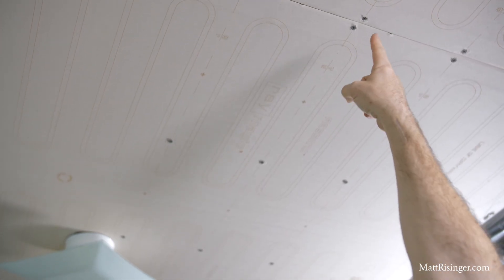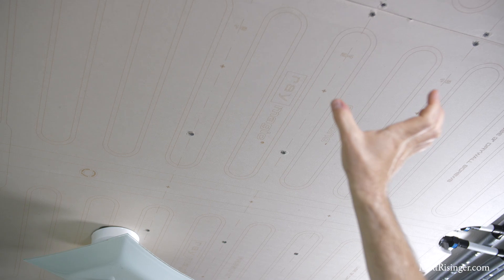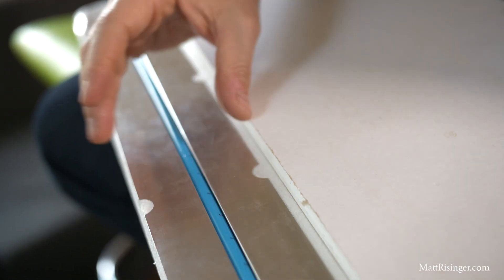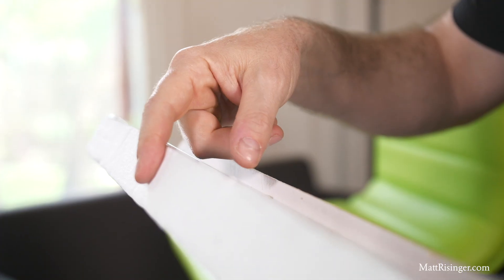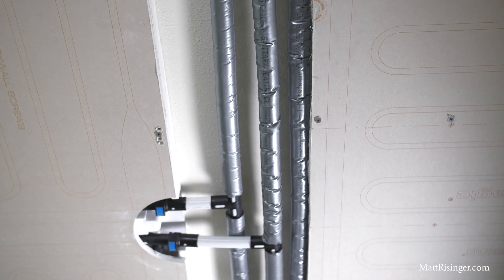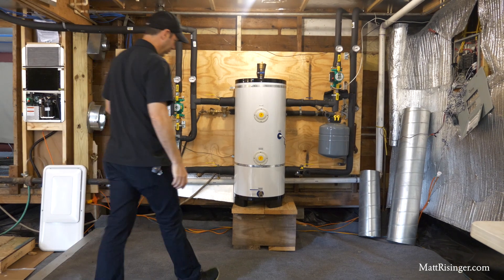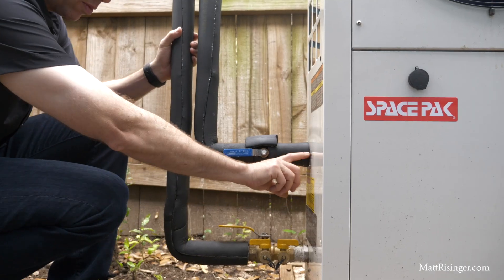Walk me through what we're seeing here. It looks like we've got four-by-eight panels that have sheetrock on them, and there's a laser-etched design that shows what the PEX tubing behind looks like — just a small thin tube. Behind that is a thin sheet of metal that's probably helping to spread out the cooling or heating effect of that tubing. Behind that is EPS foam, maybe an inch or two. And that all connects to some insulated PEX tubing, which is then headed where? It goes down into the manifold downstairs to the buffer tank, with some pumps and valves, and then it goes outside to an air-to-water heat pump.